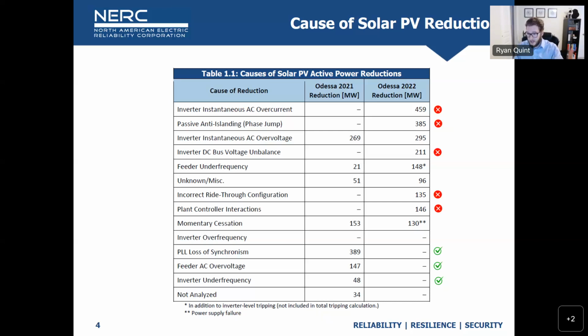So they did a bunch of analysis and disabled it. And what happens? Instantaneous AC overcurrent, AC overvoltage, and passive anti-islanding phase jump protection are right behind it to trip the inverters. We had speculated that might happen, but we needed real world data to prove it, because when we see these inverters trip, we also see them flagging on all these forms of protection. So it was a positive that we got rid of an unnecessary protection, but the downfall is there were three or four other forms of protection right behind it, ready to trip the inverter as well. This proved that was exactly the case.